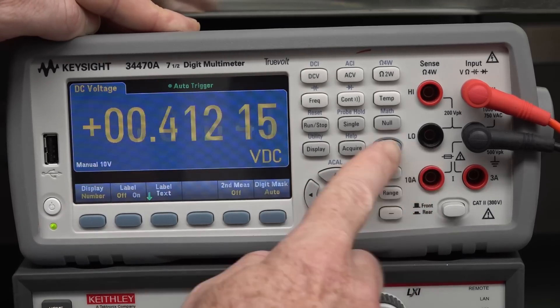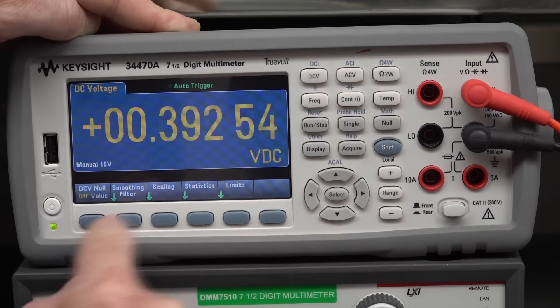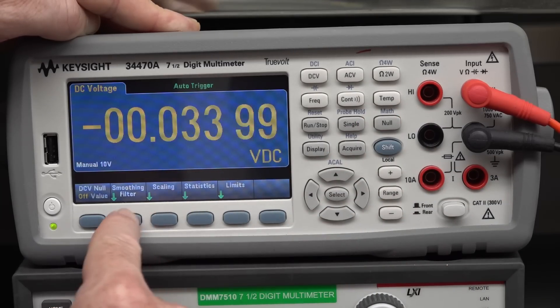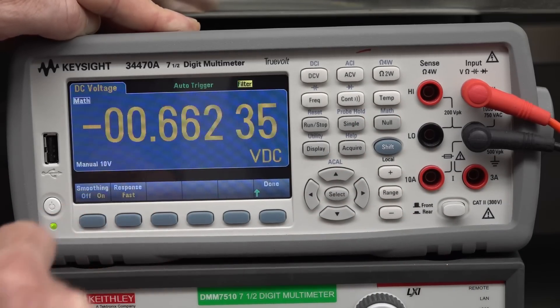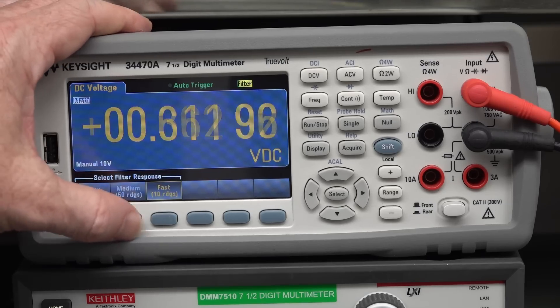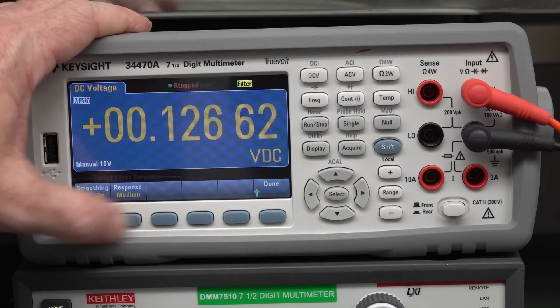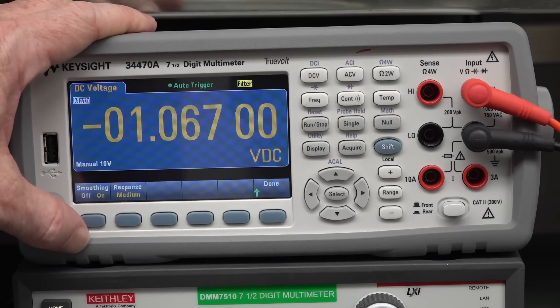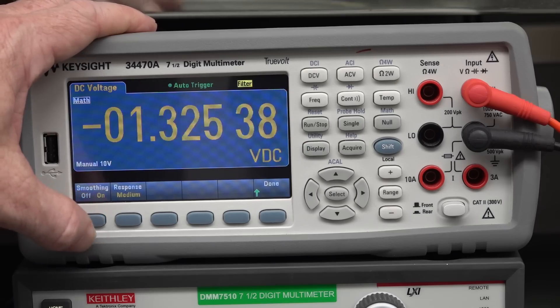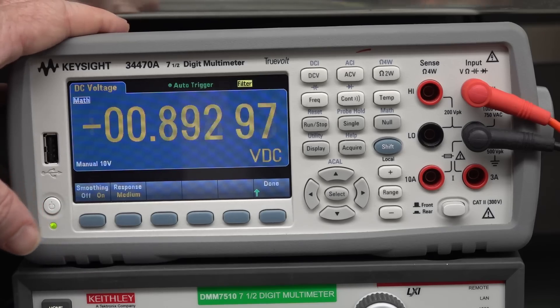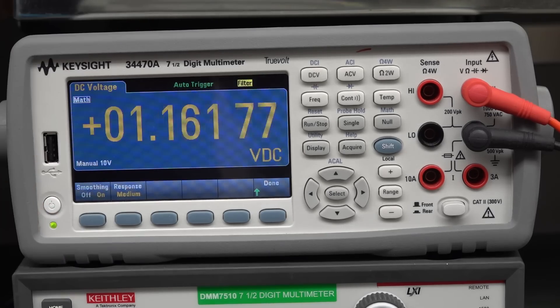And I can show you how the smoothing or average mathematical averaging doesn't do the same thing. It's actually to do with the measurement integration. Not the post-measurement smoothing or something like that. So, let's go down to 0.2 power line cycles here. And then we'll go into math up here. And, where are we? We've got smoothing filter. There we go. If we turn the smoothing filter on, it doesn't really do anything. So, it's doing, and the response also, 10 readings, 50 readings of smoothing. It doesn't help. So, doing post-sample averaging and smoothing does not help the situation.